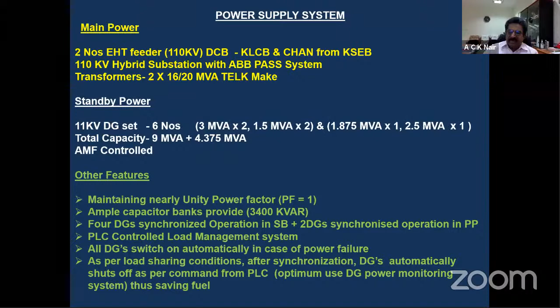Another main feature is that we maintain an almost unity power factor, and we have a capacitor bank to compensate the power factor. The DGs are synchronized in the service building. 2 DGs are synchronized in operation, and in the power plant also, with an all-PLC controlled load management system. All DGs are switched on automatically in case of power failure. As per load sharing conditions, after synchronization, DGs are automatically shut off as per command from the PLC on reaching the power conditions. So these are some of the pictures, and we have an energy policy also.